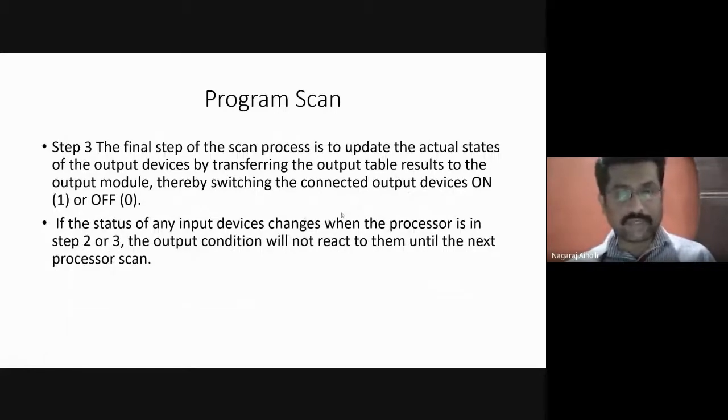If the status of any input device changes, that is the main point I highlighted, when the processor is in step 2 or 3, the output condition will not react to it until the next processor scan. If there is any change in the input status, that will be reflected only after the completion of the existing program scan. Up till its completion, it cannot accept changes in the input values.